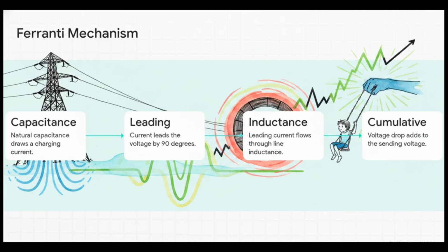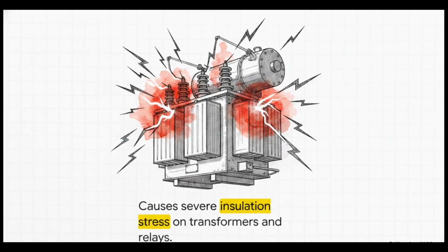It's exactly like pushing a kid on a swing at the absolute perfect millisecond. The energy cumulatively adds up along the length of the line, driving the voltage higher and higher the further it travels. Now, this isn't just some quirky physics trick you do in a lab. It is a massive problem for power operators. This over-delivery of voltage causes severe insulation stress on downstream transformers and relays. If you suddenly hit a transformer with a significantly higher voltage than it's physically built to receive, you can severely damage crucial grid infrastructure. It can even trip the distance protection relays, which could potentially cause cascading power outages. An empty line is literally a dangerous line.